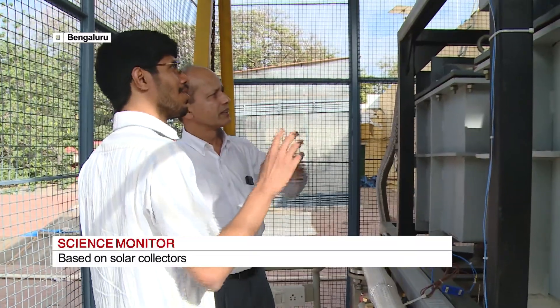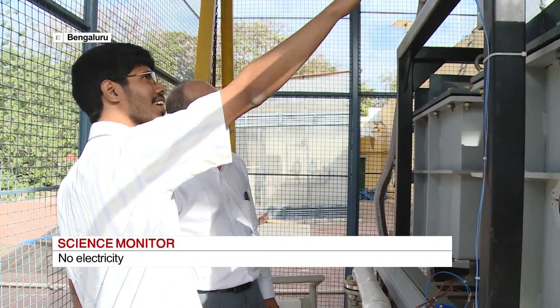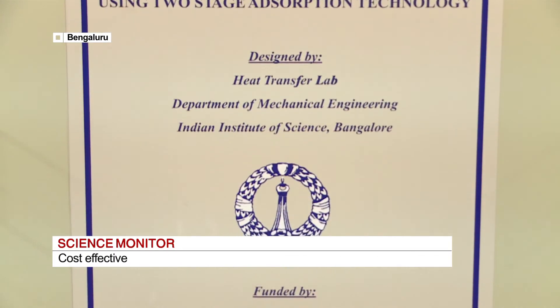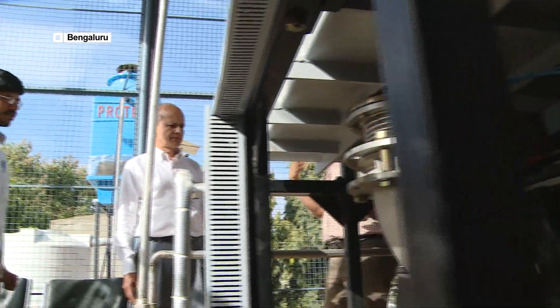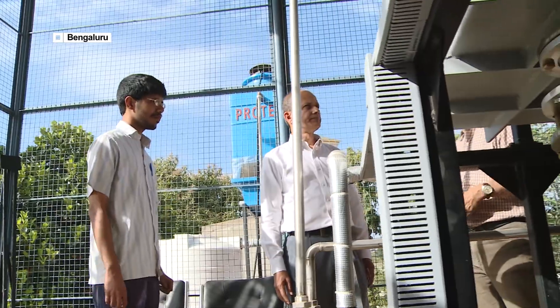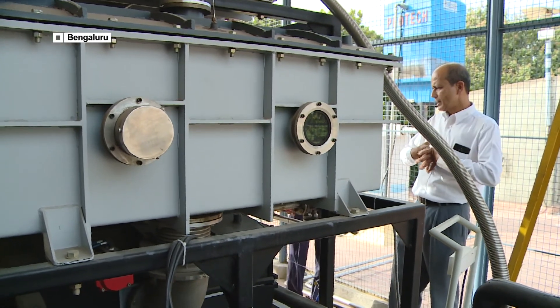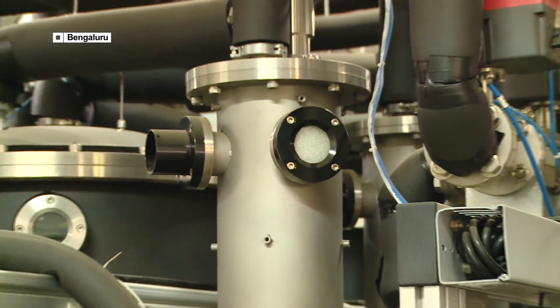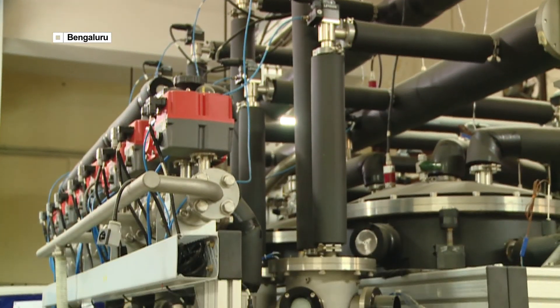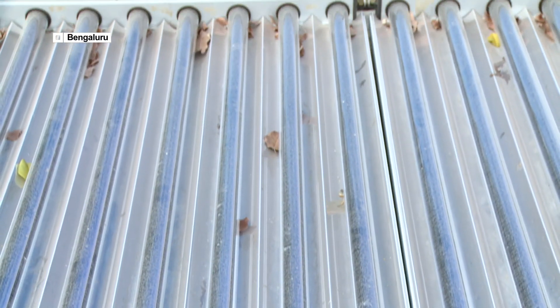This is being demonstrated as a unique laboratory scale prototype of solar coolers by the team of Professor Pradeep Dutta from the Indian Institute of Science, who has developed this technology under the aegis of the Department of Science and Technology. The solar cooling technology is based on the use of low-grade thermal energy, preferably below 100 degrees Celsius. Researchers have used a silica gel and water adsorption system which can operate within 75 to 85 degrees Celsius, easily attained by solar collectors.